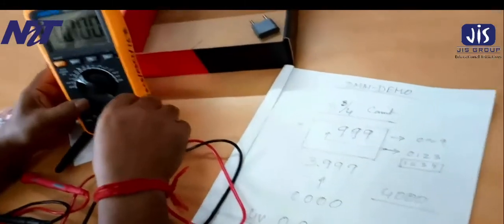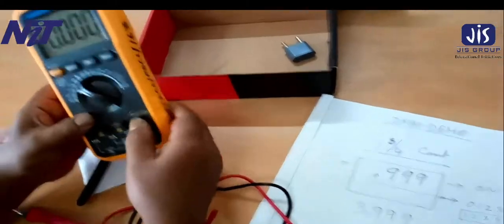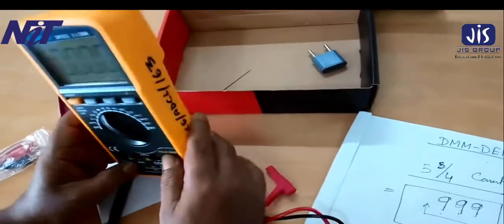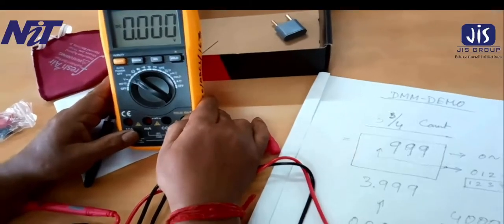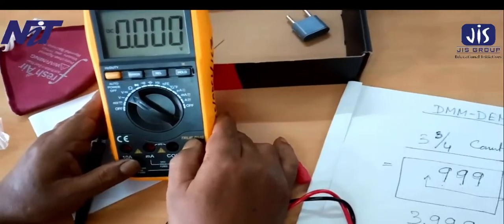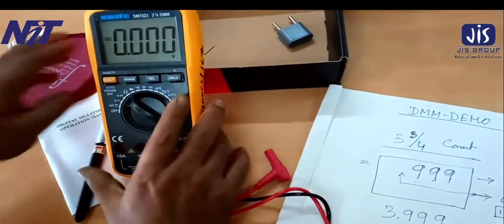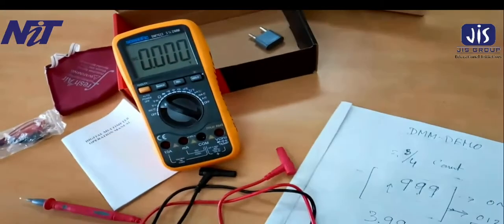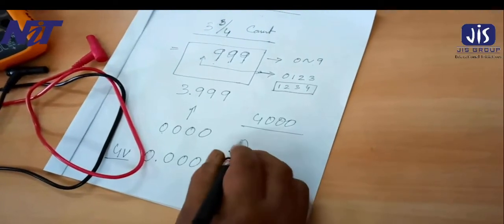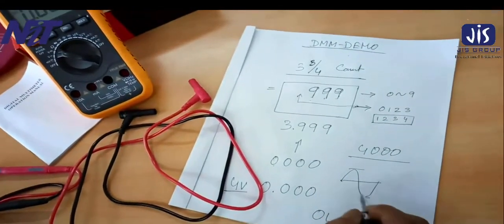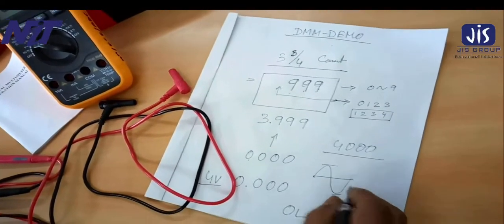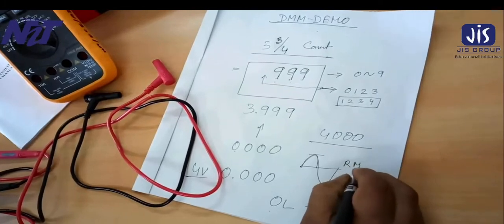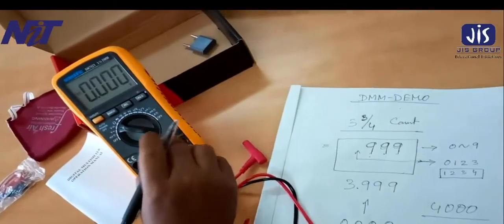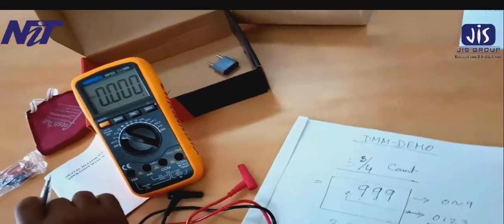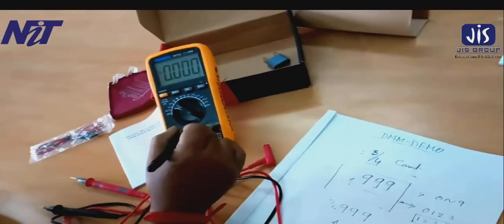Okay. And another exclusive feature in this meter is true RMS. True RMS means that in a digital multimeter you must remember that it cannot display the peak-to-peak voltage as a CRO does. The CRO is the only instrument which can display the peak-to-peak voltage of any signal directly. But in a multimeter, if you measure a sinusoidal or alternating current signal, you get only the RMS value of this signal. Not all meters are capable of this RMS measurement. This meter has the facility to determine the true RMS value.